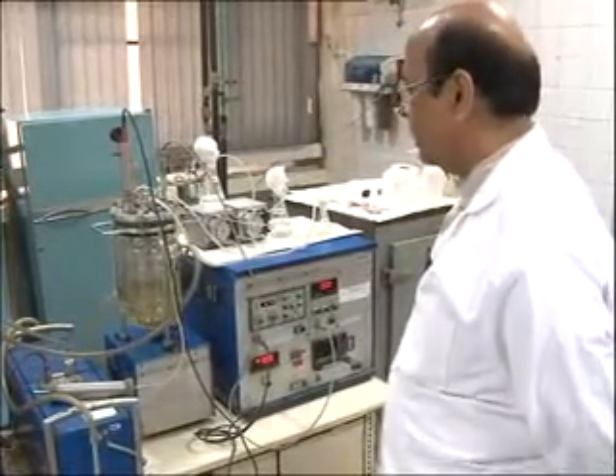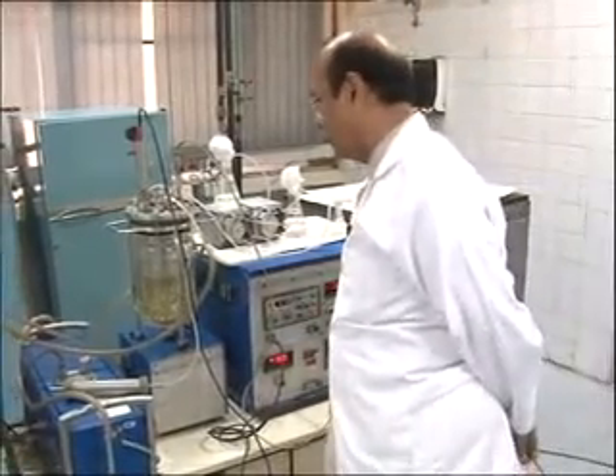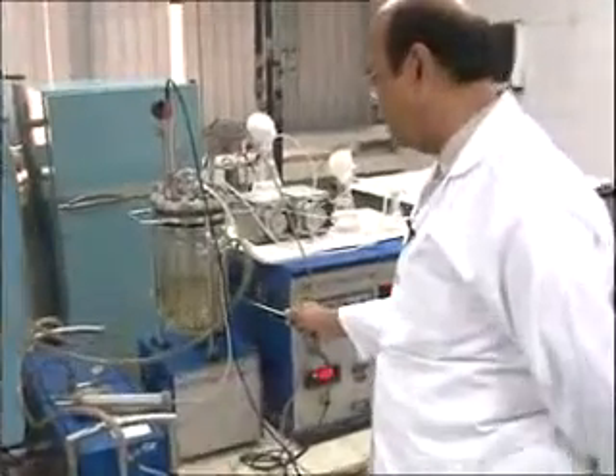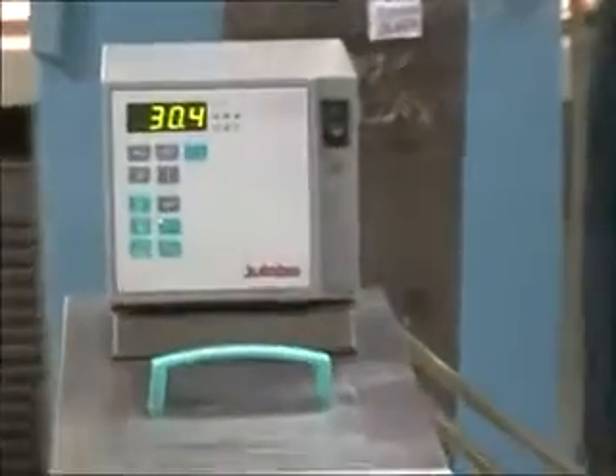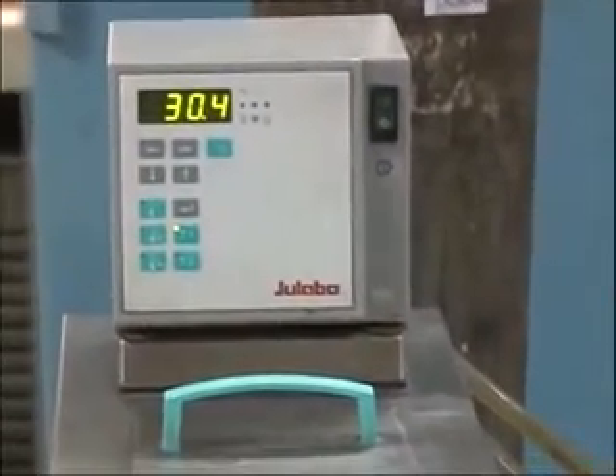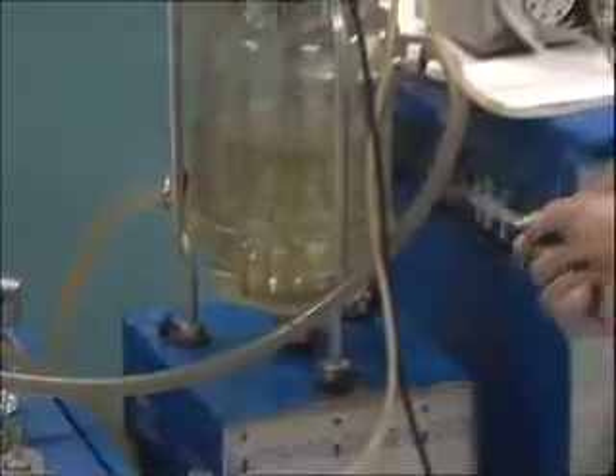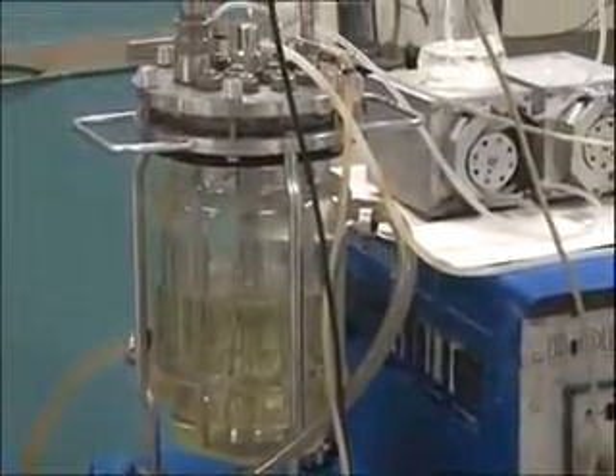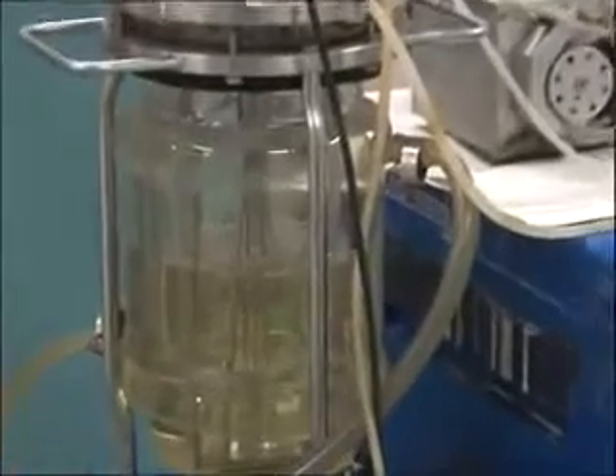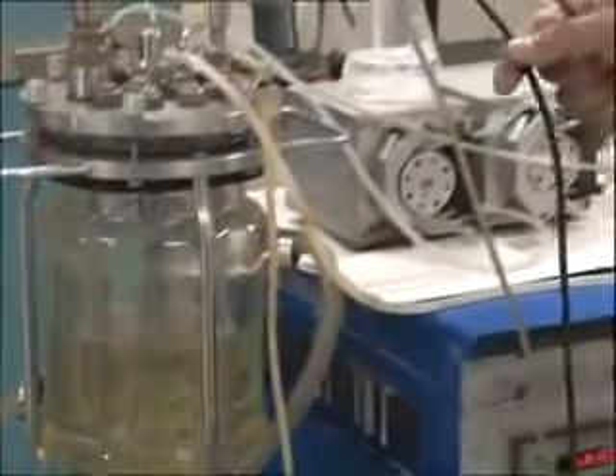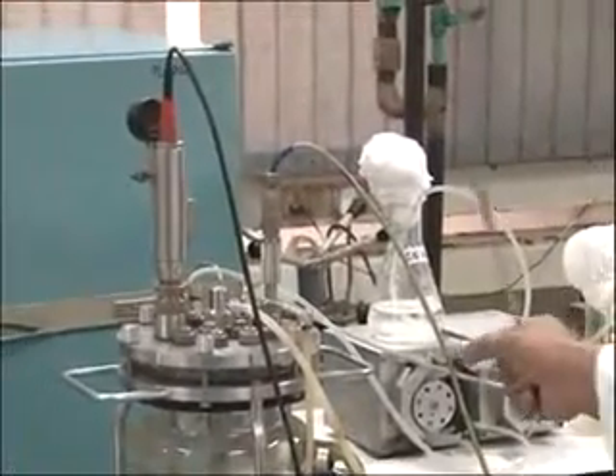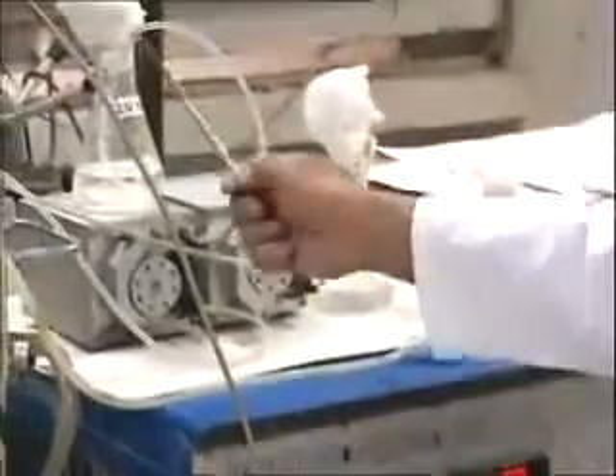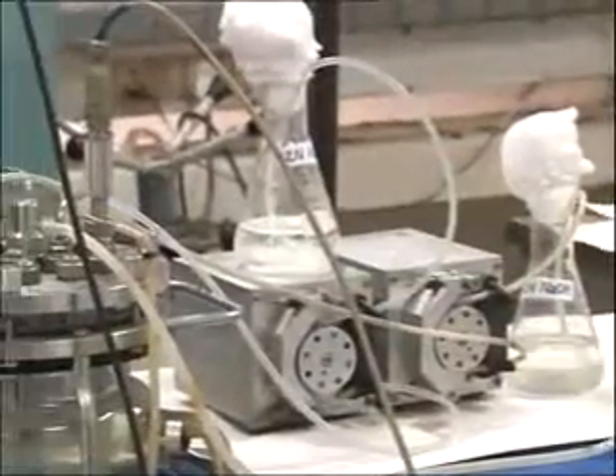After it has been cooled down, we connect all the lines for the control of temperature. So we have water inlet and water outlet over here. This is a chiller. We maintain a temperature of 30 degrees, which is the desired temperature of the fermentation in the bioreactor, and pass the water of this 30 degrees centigrade in the jacket, so as to maintain 30 degrees in the bioreactor. We have also connected the pH probe to the controller unit, the DO probe to the controller unit. As you see over here, acid and alkali lines have been connected to the bioreactor at appropriate places.